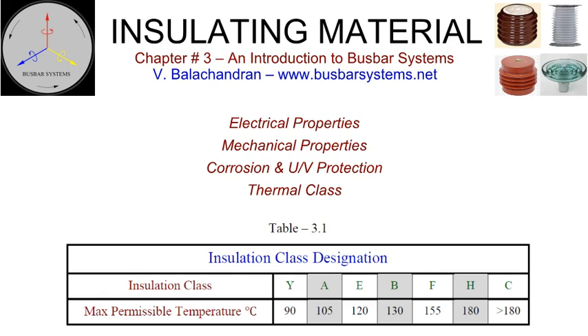Corrosion and ultraviolet resistance. Insulating material must be suitable to withstand the ambient atmosphere, which may be corrosive. Insulators exposed to the atmosphere must also have resistance to ultraviolet radiation. Most insulators have metal parts embedded at either end for connections. While the insulating material is susceptible to degradation due to ultraviolet radiation and corrosion, the embedded inserts and metal parts are susceptible to corrosion. Thermal class. The thermal class of insulation must meet the requirements of the envisaged temperature of the conductor during operating conditions. For most busbar systems conforming to international specifications, Class B insulation will meet the requirements. Selecting a higher class of insulation, believing it to provide a higher safety margin, does not improve the life or performance of the product, and only serves to increase the cost.